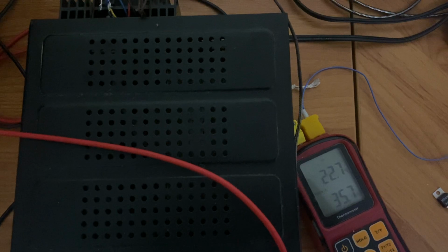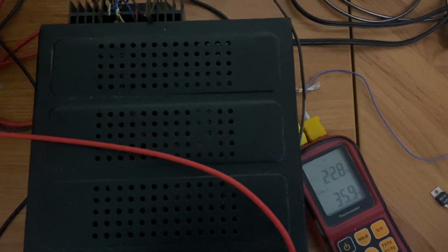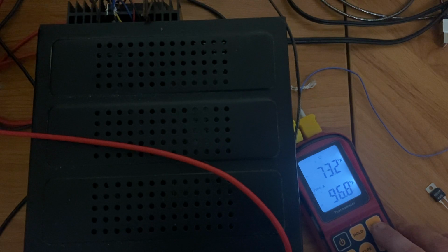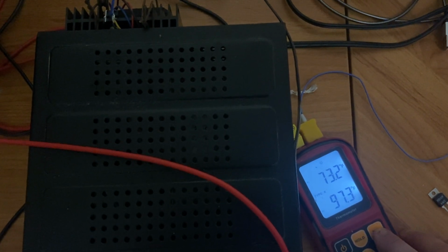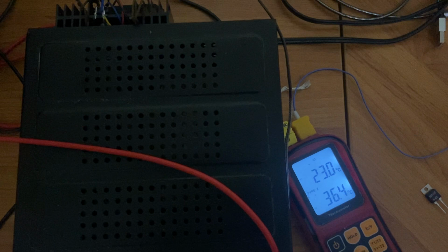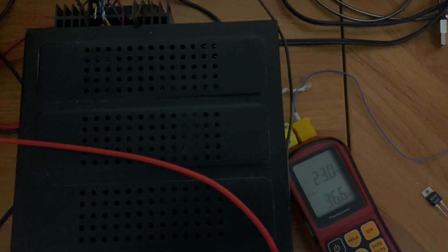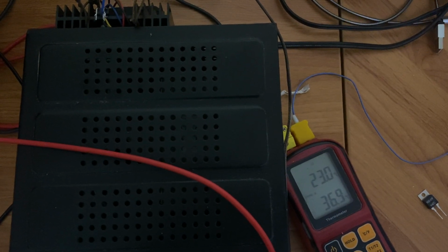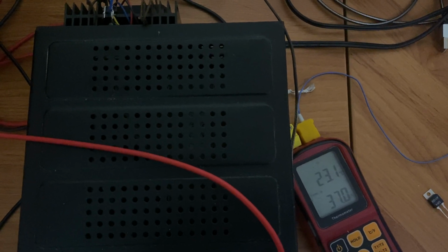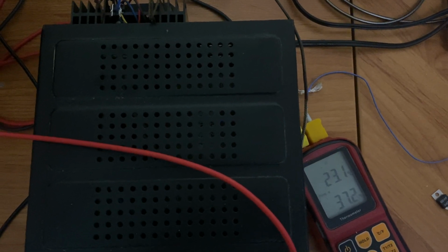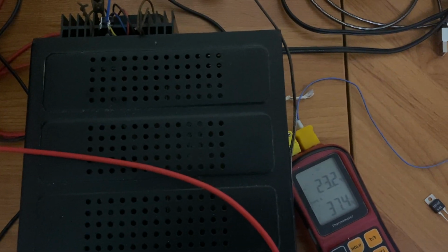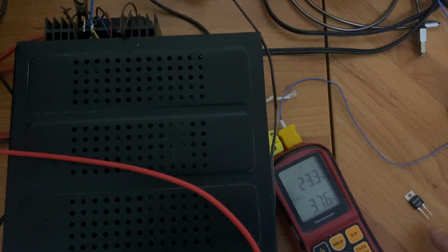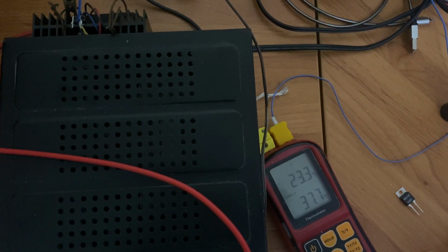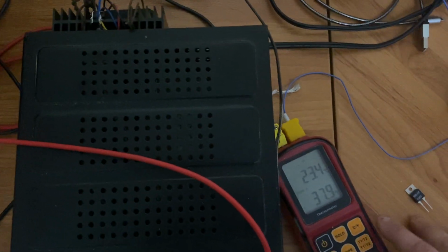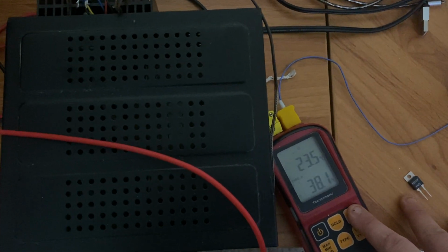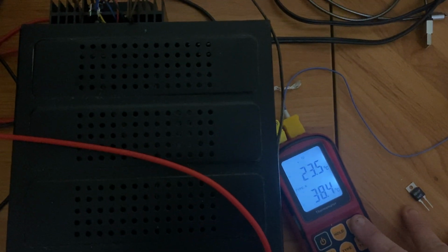We're currently at 35, and it didn't want to focus. Getting close to 100 degrees Fahrenheit, which is 36.5 degrees. Now, as soon as this thing does kick on, I'm going to shut the load off so it'll instantly start cooling down with the fan. Again, the thermal switch is rated for 45 degrees Celsius, which we're coming up on. There's 38 degrees Celsius, which is 100 degrees Fahrenheit.